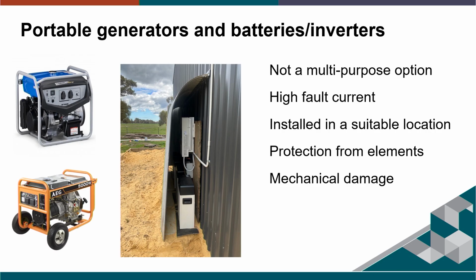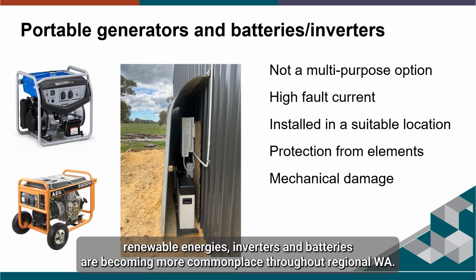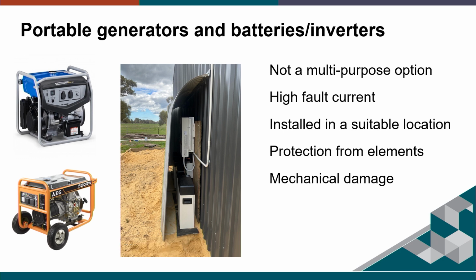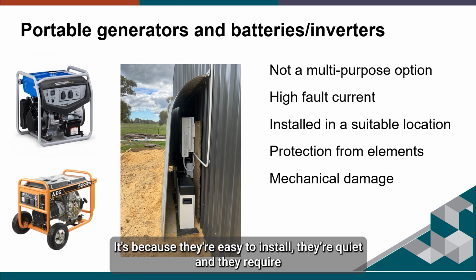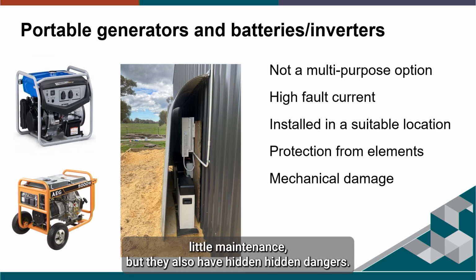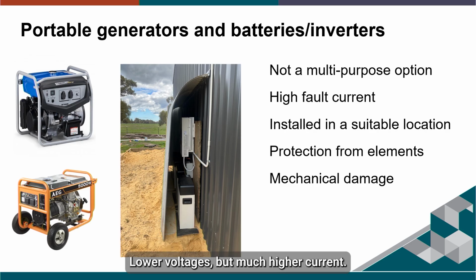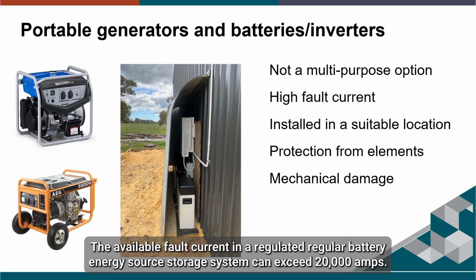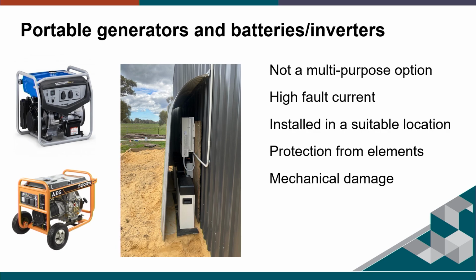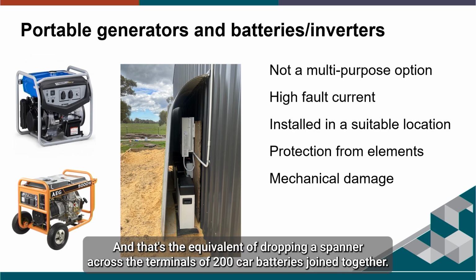Be mindful of that. With the push in renewable energies, inverters and batteries are becoming more commonplace throughout regional WA. It's because they're easy to install, they're quiet, and they require little maintenance, but they also have hidden dangers. Lower voltages, but much higher current. The available fault current in a regular battery energy storage system can exceed 20,000 amps. And that's the equivalent of dropping a spanner across the terminals of 200 car batteries joined together.